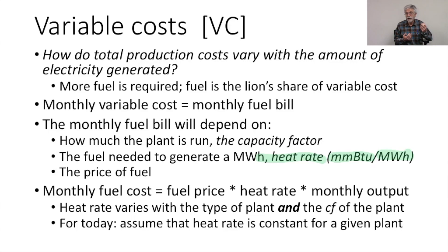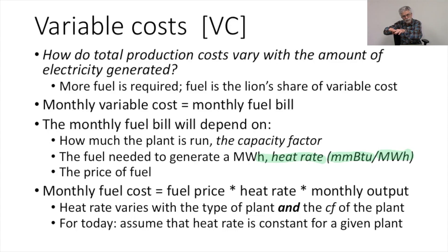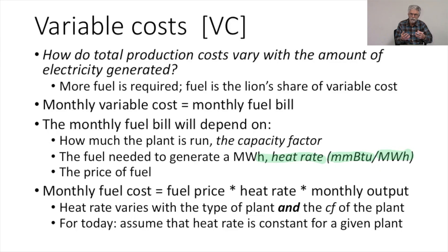In fact, the same power plant may have different heat rates at different capacity factors. The heat rate may be very high at really low capacity factors, but then it falls into a more efficient range as we get into the normal operating range of the power plant. And then if you push the power plant really hard up to its extreme design capacity, the heat rate might start to rise again. Each plant will have its own characteristic heat rate at different capacity factors.